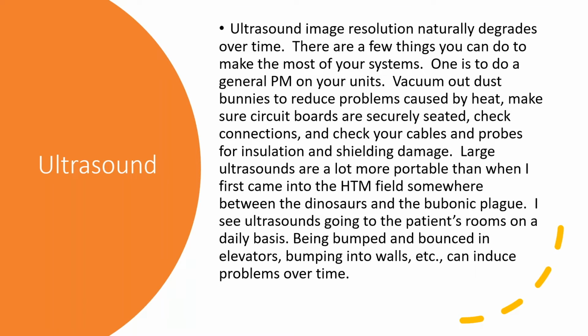Well, if it's not required, unless you're doing an AEM where you require it and you have a general procedure instead of following the OEM, then yeah, then you would. And what we're doing is, I have Rachel, my imaging technician, and she will do a general PM on it, vacuum out the dust bunnies, and also take an ultrasound phantom and QC all the probes. And this hadn't been done. We didn't have a dedicated imaging person for about 3 years. And so a lot of things would fall through the cracks.